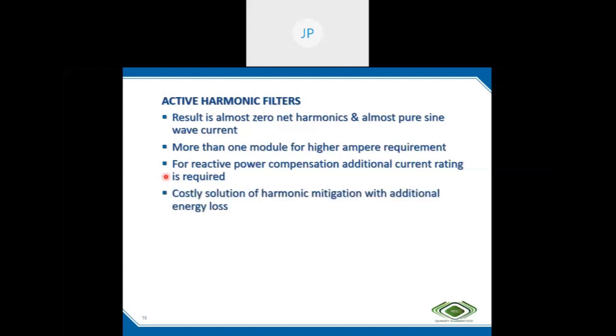And above all, this is also a power electronic device. Its switching frequency is high, so it also generates high order harmonics, maybe about the 25th, 27th, like that. Some equipment is very sensitive to these high frequencies, so such locations are not advisable. The advantage is that it does not require too much harmonic study.